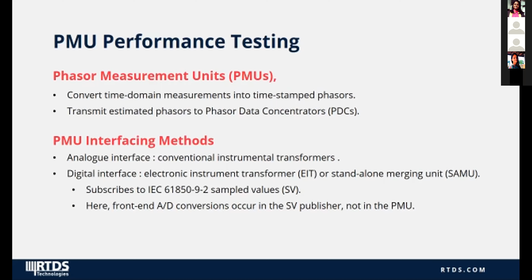The first one is the analog interface. It uses output from conventional voltage and current transformers. PMUs with analog interfaces need to convert the analog input signals into digital signals. The second uses electronic instrument transformers, or EIT, or a standalone merging unit. PMUs with digital interfaces subscribe to IEC 61850 sampled values.